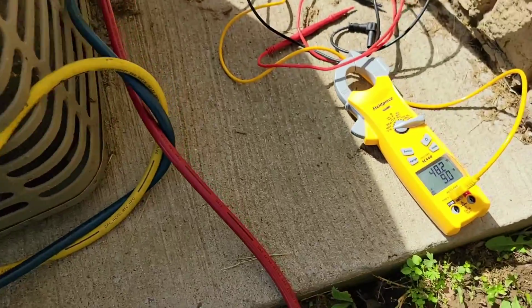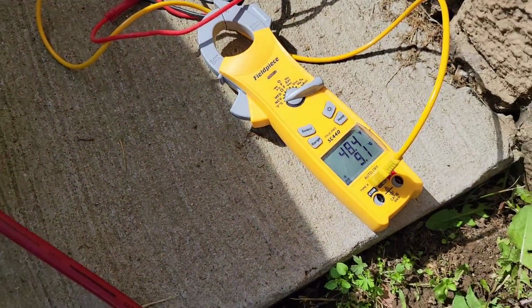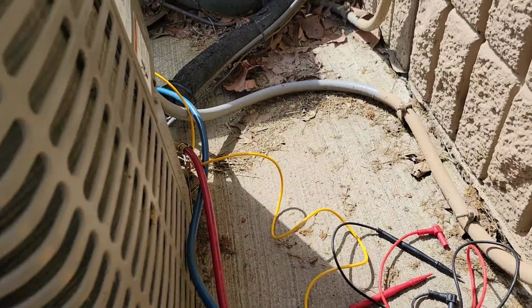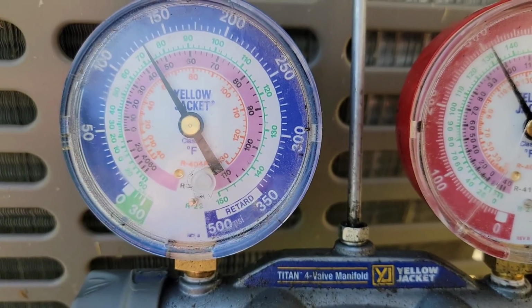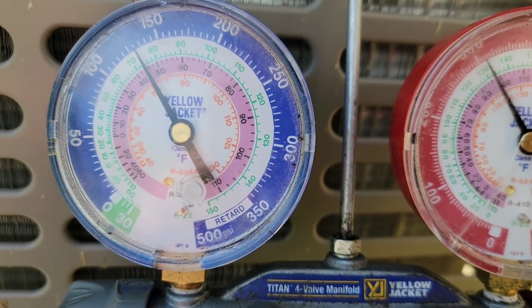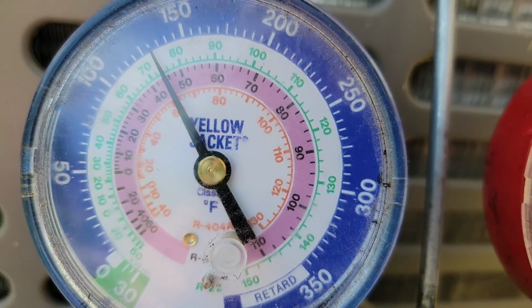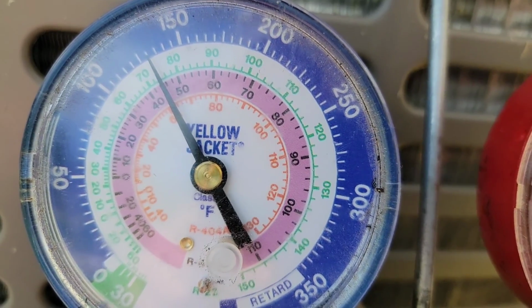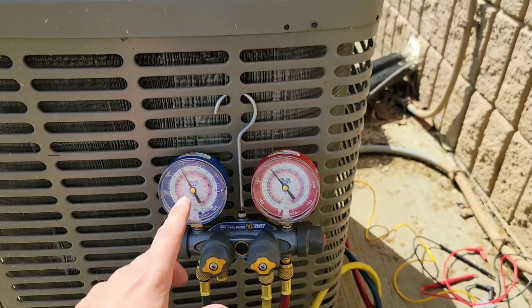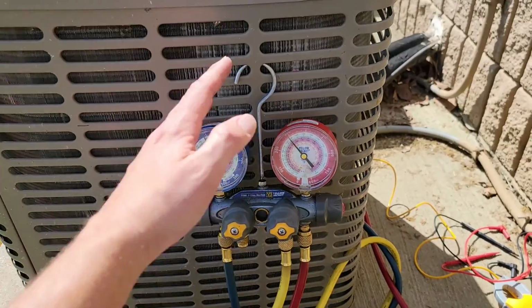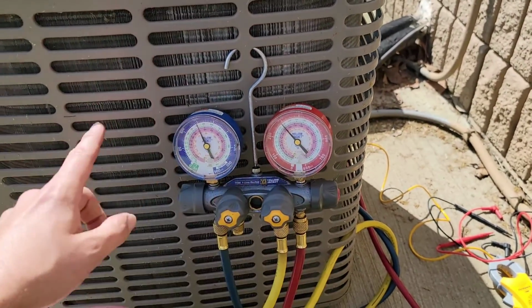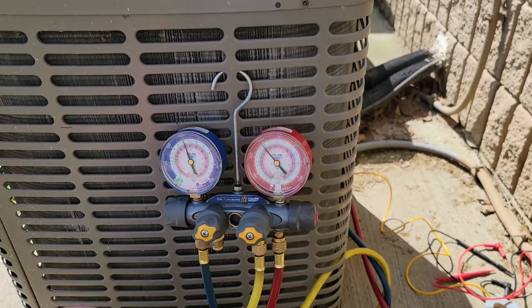All right, this unit's charged as well. 48 degrees, wow, on the vapor line going in. That's nice. And our superheat, since we have 48, and then over here we have about 44, superheat on this is about 5 degrees. Definitely check subcooling though. If you want to know how to check superheat and subcooling, again, go to my playlist, HVAC Tips for Technicians.